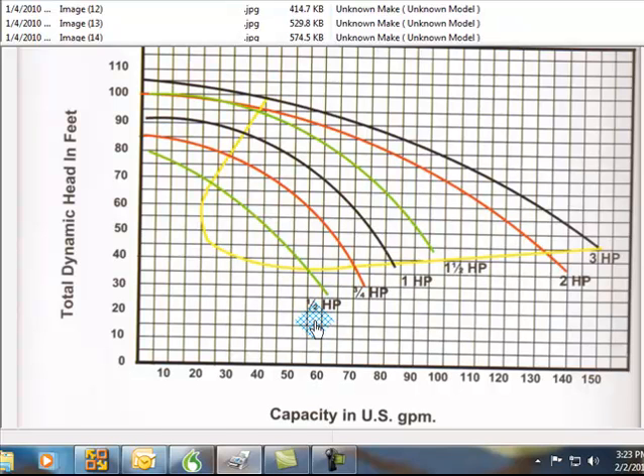You have to calculate all your pipe, know exactly how many 90s, how many 45s you have in the line. So, for argument's sake, you're 50 feet away from your pool to your pump, and you could be at 110 feet real easily between your suction, and you have to figure in some more for your filter.